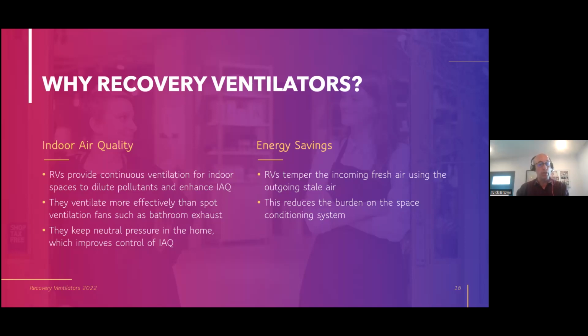They also keep neutral pressure in a building. Neutral pressure is important because anytime you have a pressure imbalance across the building envelope, it's an opportunity for indoor air quality problems. You can assume with an exhaust fan running in a building, negative pressure in the building, you're sucking in outdoor air in an uncontrolled way from various places at various times when you may not want that outside air coming in an uncontrolled way. So really neutral pressure allows for enhanced control of indoor air quality.